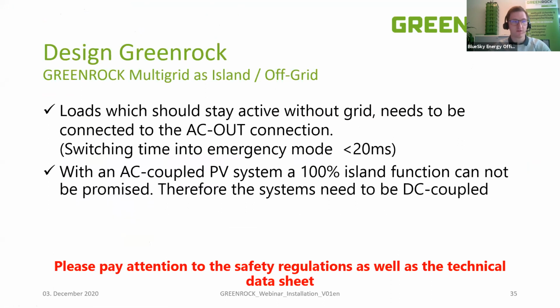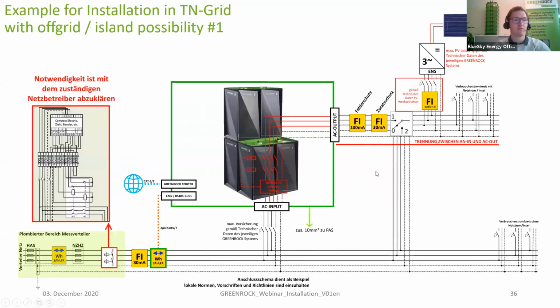But what you can also do is an island system. So not only backup off-grid, you can even go to a backup off-grid island system, which means the PV inverter is now not connected to the grid in parallel, but it is connected on the AC out of the system. But also in this connection, the PV first ensures that all the loads are covered, and the battery system waits until all the loads are covered. And only if energy would go into the grid, the battery starts charging. So this main function always stays the same. No matter how you connect the system, this function will always stay the same. First, all the loads are covered, and if energy would go into the grid, the battery starts charging.